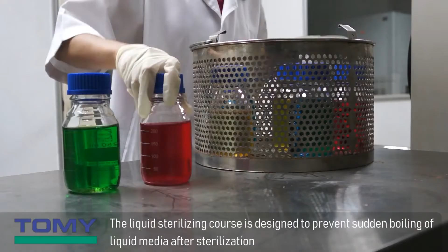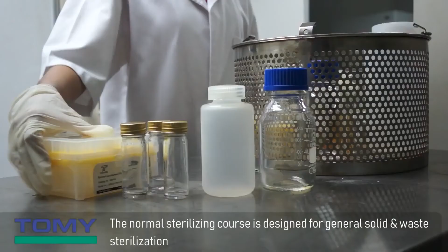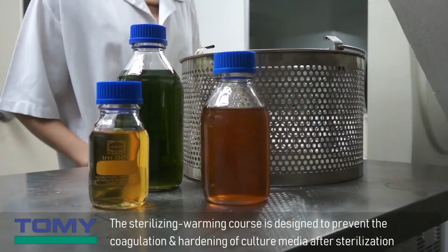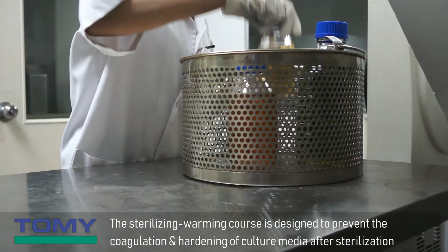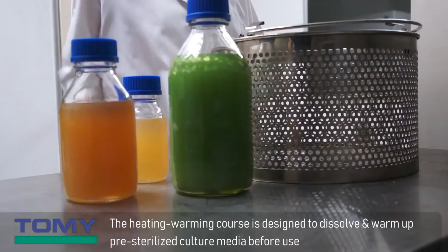The liquid sterilizing course is designed to prevent sudden boiling of liquid media after sterilization. The normal sterilizing course is designed for general solid and waste sterilization. The sterilizing warming course is designed to prevent the coagulation and hardening of culture media after sterilization. The autoclave does this by maintaining a specific temperature for a period of time after sterilization.